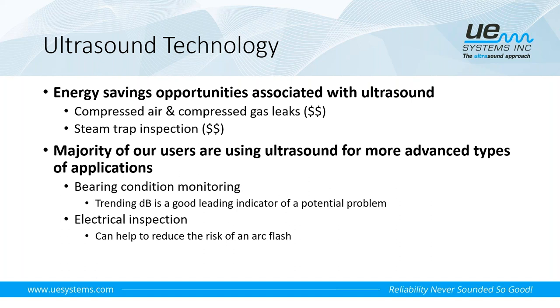The primary driver for this application is safety. We're seeing more and more users use ultrasound in conjunction with traditional infrared scans of energized electrical equipment, where we can listen first before we ever open anything up to do an infrared scan or a visual inspection. If you have faults like corona tracking or arcing taking place inside your equipment, that sound will exit out wherever there's an opening. So we can simply scan around the seal of the cabinet door, louvers, and vent openings, and be forewarned about any potential problems before we open up that piece of equipment. In a way, it helps reduce the risk or the chance of an arc flash.